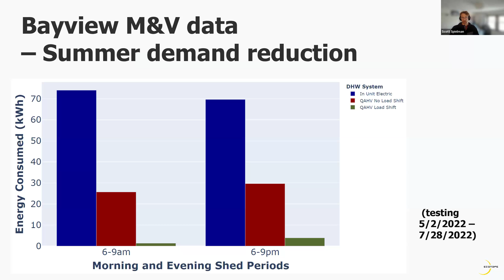As far as modeling efficiency, if you're looking for just a quick COP value that you can use to look at an annual savings from a heat pump water heater versus a gas or electric resistance system, I'll recommend that you look at the Northwest Energy Efficiency Alliance qualified products list. There's a qualified products list posted on their website. You can look at the PDF, and it has a couple hundred of these full systems from different manufacturers and distributors where the annual system COP, so that's not just the COP of the heat pump itself, but it's the whole domestic hot water system to provide the recirculation heating and the primary heating of incoming cold water.